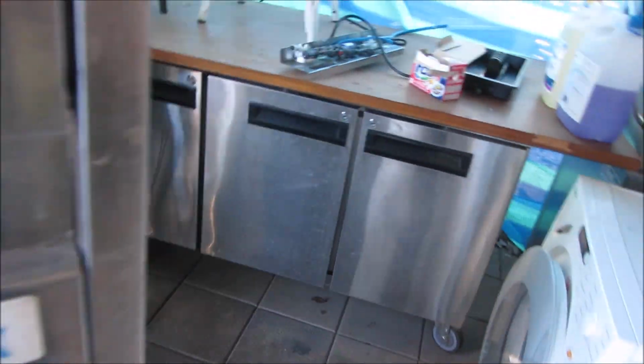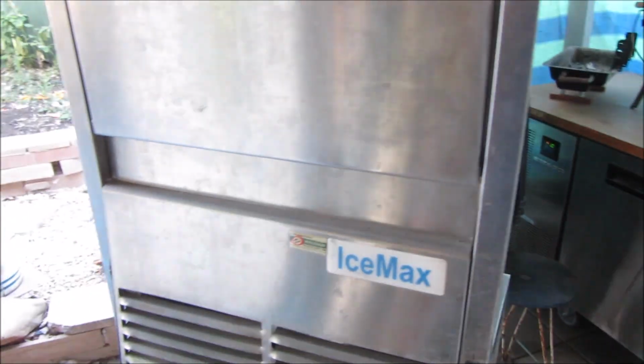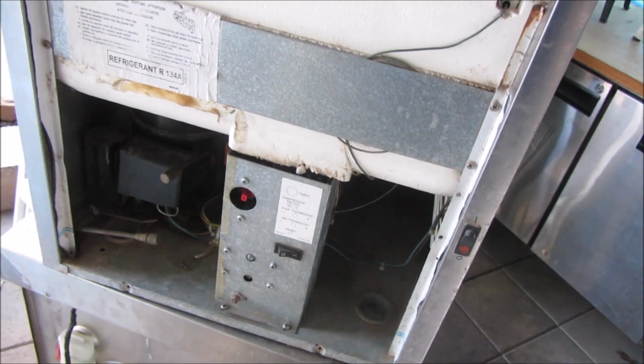Anyway, with this one here, this one does work, but it'll freeze up the evaporator, and it's supposed to freeze the evaporator to a certain degree. Once it harvests ice, it's then supposed to start the timer, and by the time that timer hits defrost, this is all full of ice and dumps it.